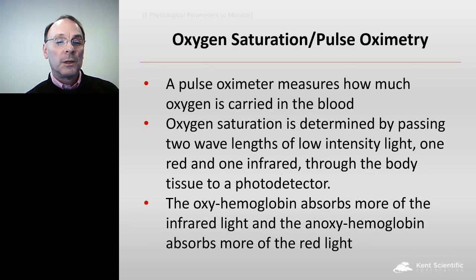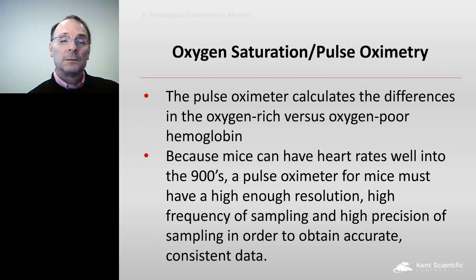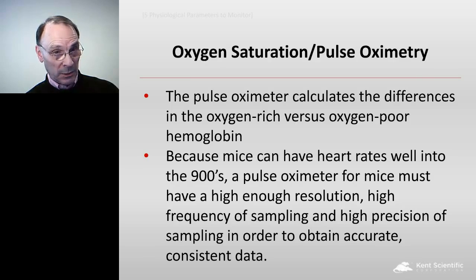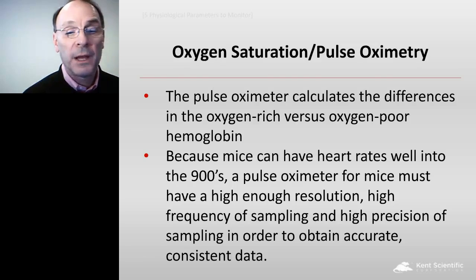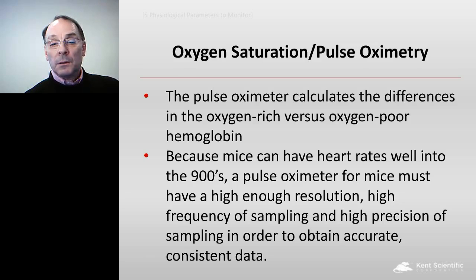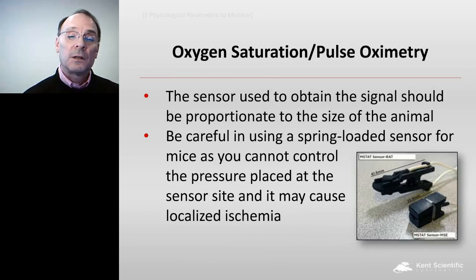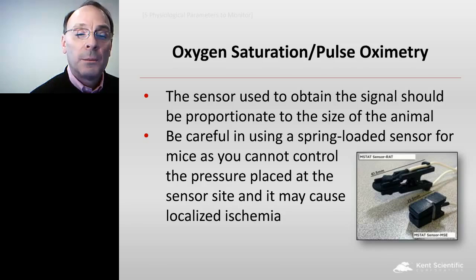Pulse oximetry measures how much oxygen is carried in the blood. Oxygen saturation is determined by passing two wavelengths. We could go into that deeper, but looking at our time and the things to cover, we don't need to get into that too much. The pulse oximeter calculates the difference between oxyhemoglobin and deoxyhemoglobin, and the newer pulse oximeters that are designed specifically for laboratory animals can go up to 900 beats per minute. A typical veterinary-style pulse oximeter only goes up to 450 beats per minute. Also, the sensors that are used are specifically designed for the mouse.